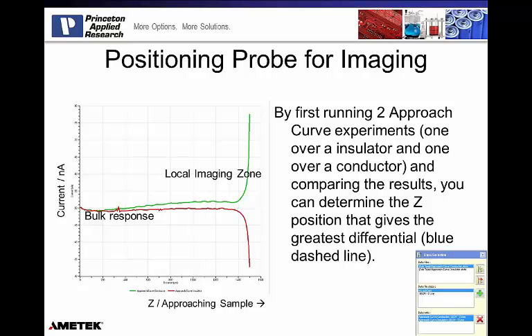So you can see, think all the way back as we talked about spatial resolution, the drive is to go to lower and lower probe diameters, smaller and smaller probe diameters. What that does is force that bulk response to a lower and lower level. That complicates or decreases the ability to see and to image over insulators and conductors. The ratio of the insulator and conductor to background becomes smaller, and that's seen as the effective decrease in electrochemical sensitivity.